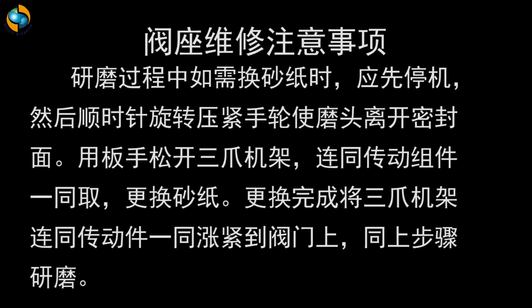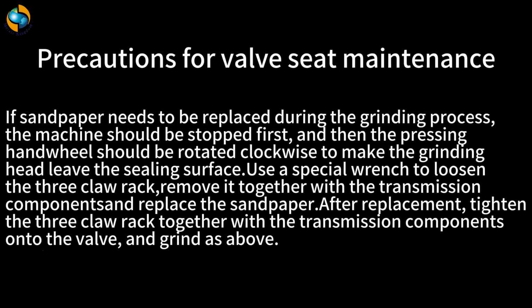Precautions for valve seat maintenance. If sandpaper needs to be replaced during the grinding process, the machine should be stopped first, and then the pressing handwheel should be rotated clockwise to make the grinding head leave the sealing surface. Use a special wrench to loosen the 3-claw rack. Remove it together with the transmission components and replace the sandpaper. After replacement, tighten the 3-claw rack together with the transmission components onto the valve and grind as above.